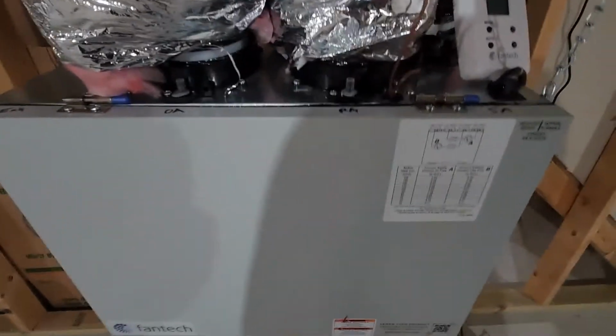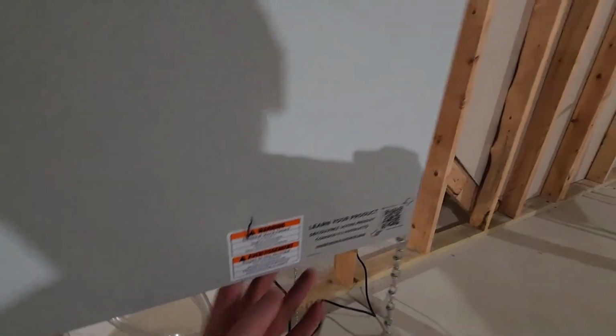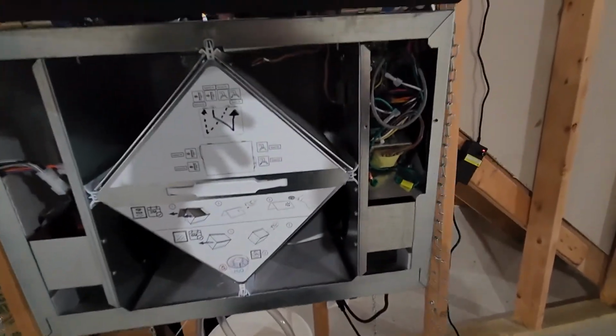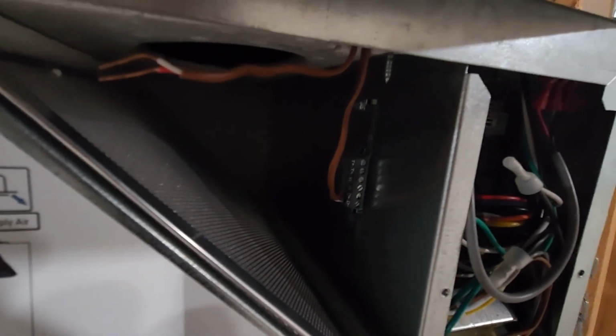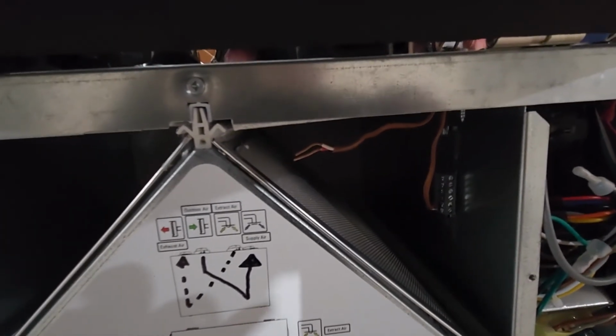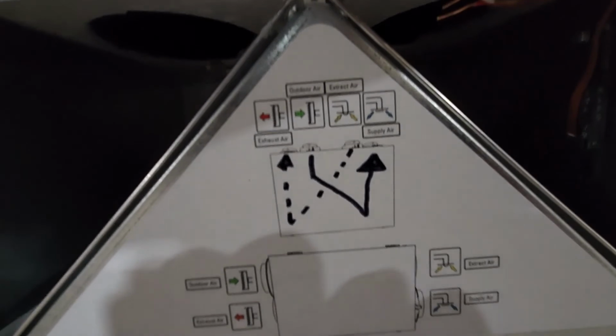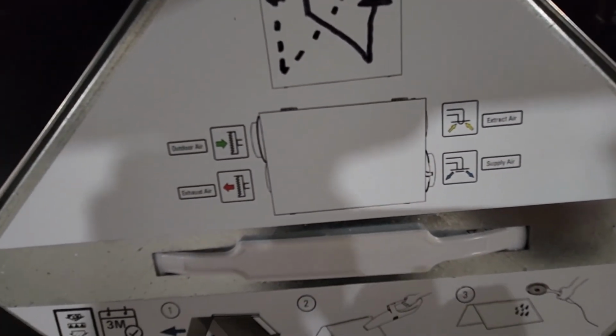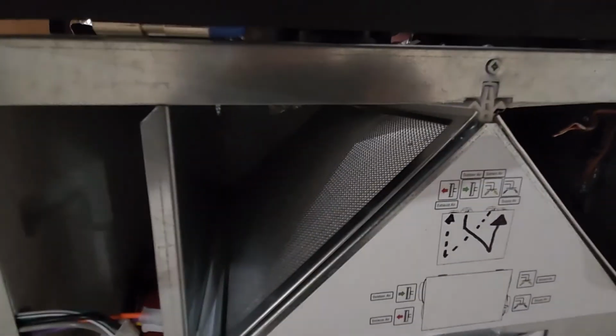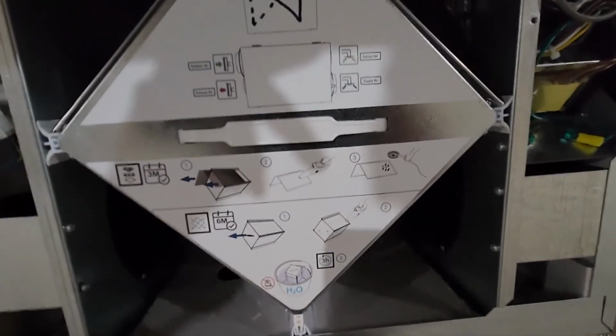So let's go ahead and open up, check out the guts inside the ERV. There's a latch on the bottom of this, 2 latches, one on each side. So you can see here's where your 3 wiring harnesses are connected. Right now I've only got the H plus and minus connected, but at one point I did have the EDF7 control connected to its wiring harness. You've got my nice hand drawn diagram here of the 4 airflow sources, and they include this nice graph for you. You've got your core with the 2 filters and your handle, and then you just slide out that core when it comes time to clean it. And here's your two fans as well, one on each side.